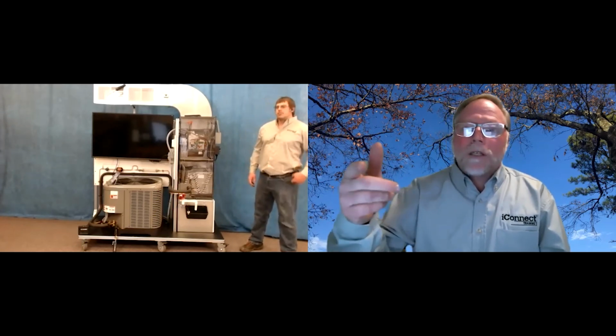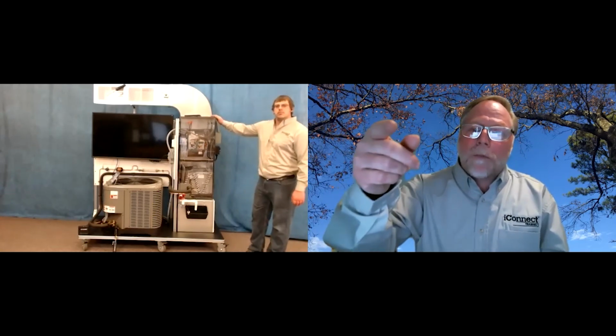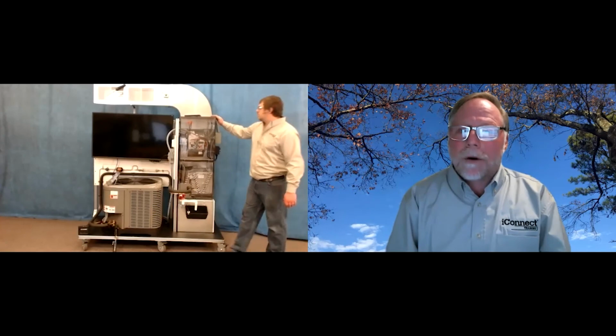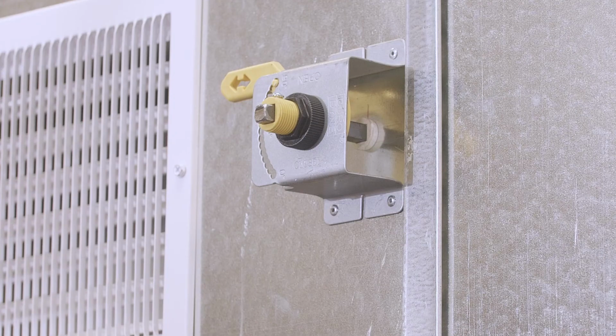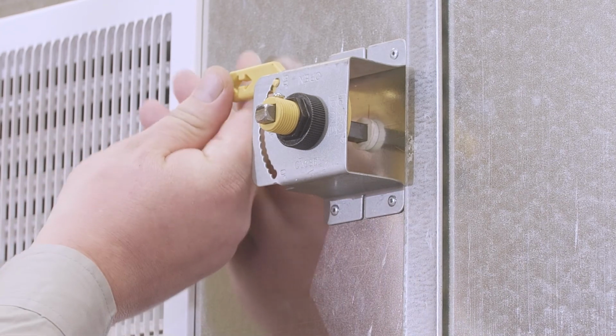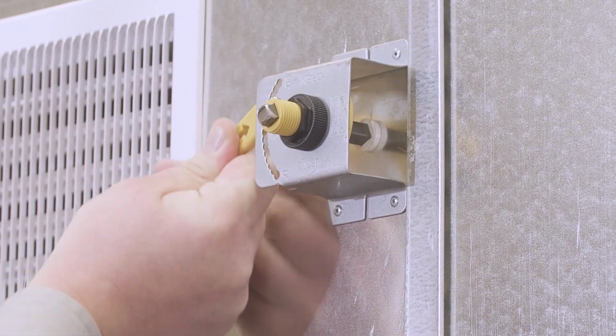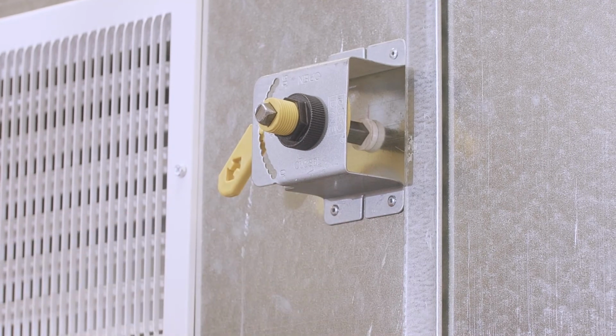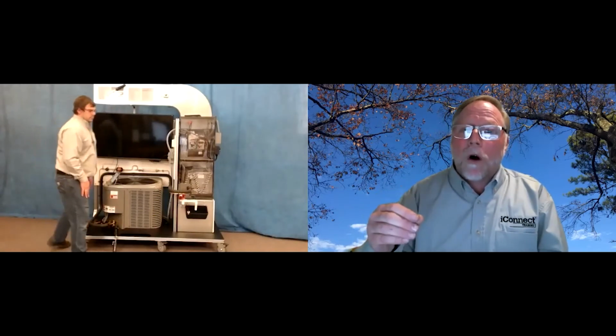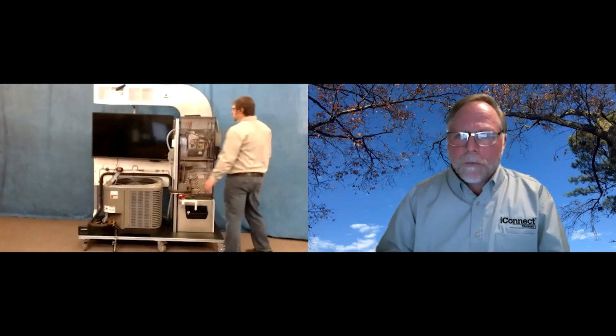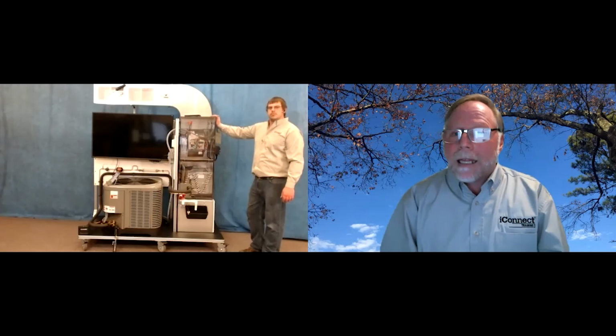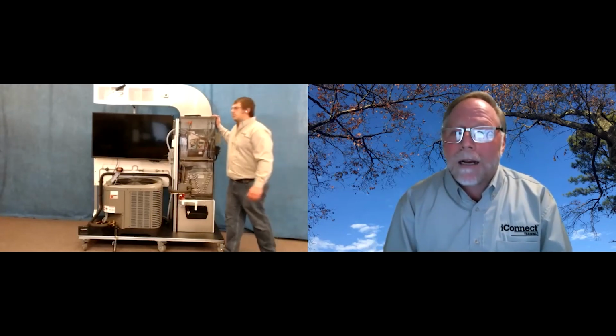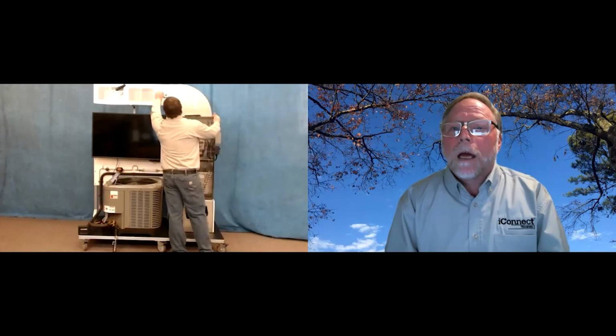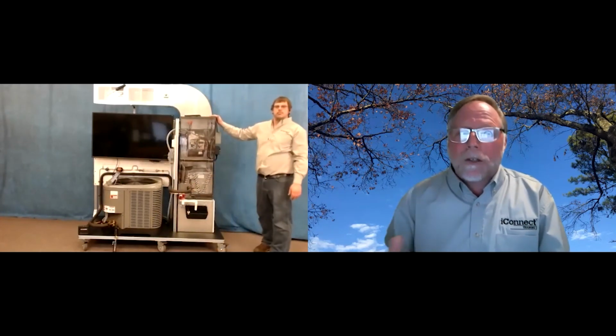So for instance, you reach up there and you can create a restriction right there with that damper. So go ahead and adjust that damper a little bit just to show how it works. And what we're simulating there is an increase in static pressure. So that would simulate too small a ductwork. And then the student can actually see the effects of the amp draw on the motor itself. And so that was one of the things that I really like about this trainer. We can show that. And then if you reach up there and open that damper back up, Nick, then they can see that the amperage on the motor will actually increase.